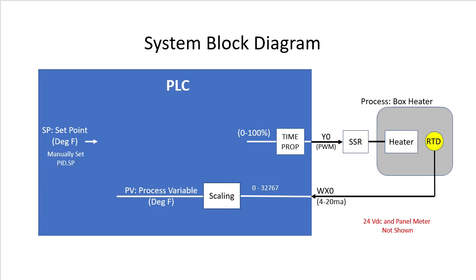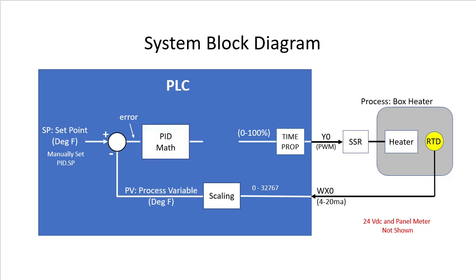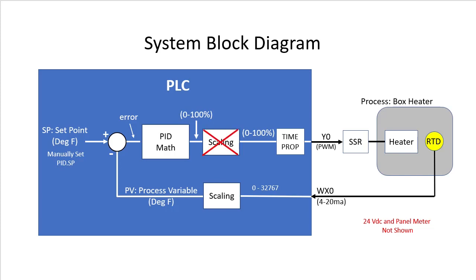Now that they are both in degrees Fahrenheit, we can subtract them to see how far apart they are. We call that the error. We then do the PID math which outputs a 0 to 100% range. Normally, we would scale that to whatever the process needs. But our process happens to need 0 to 100%. So do we need scaling? Nope.